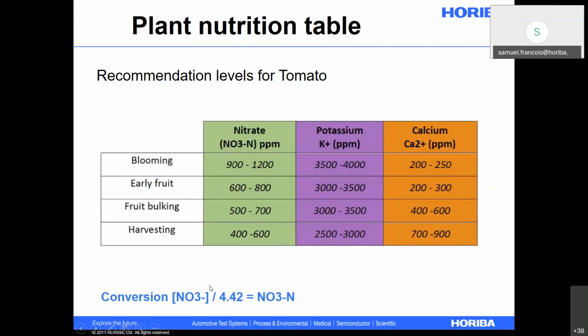NO3-N is actually the nitrogen part of the nitrate molecule. So we only express the nitrogen of the nitrate molecule. But the meter can do the conversion. We can select the meter and set the meter with the requested unit. So we have the option between nitrate or nitrogen. Okay, and basically the factor is the nitrate concentration divided by 4.42 gives us the nitrogen concentration.